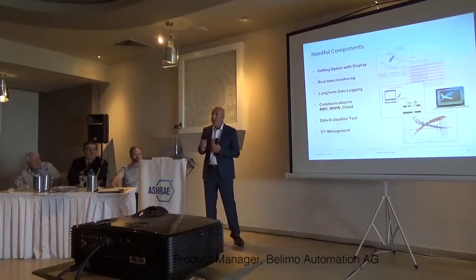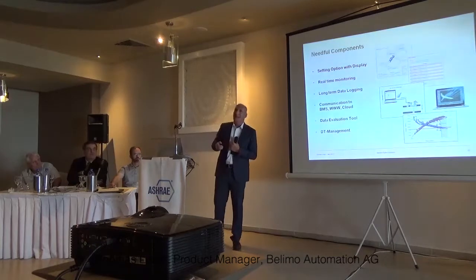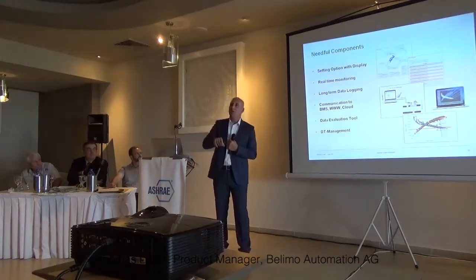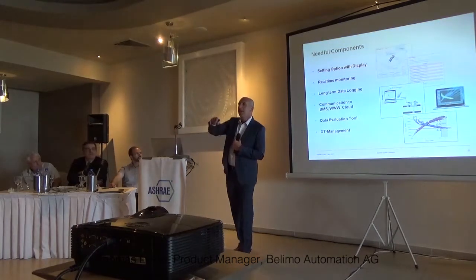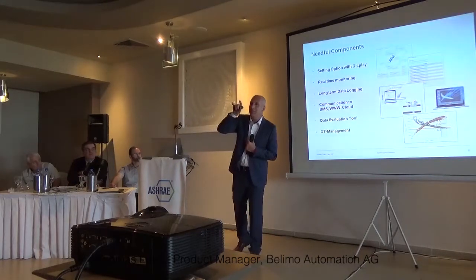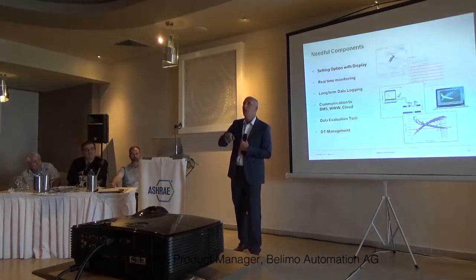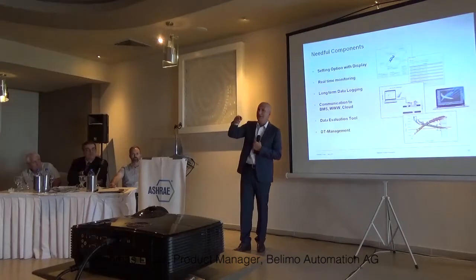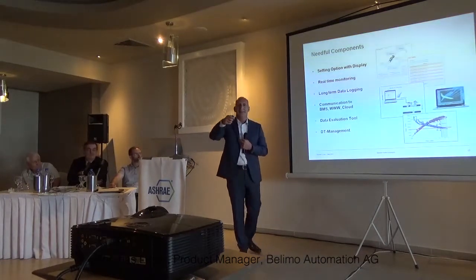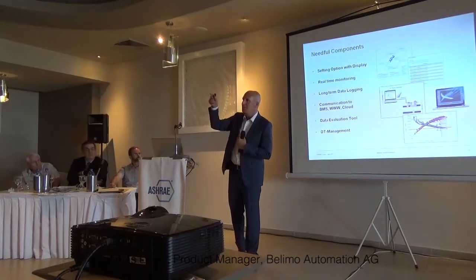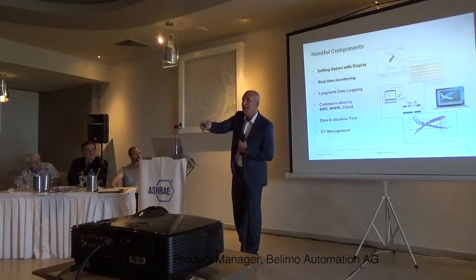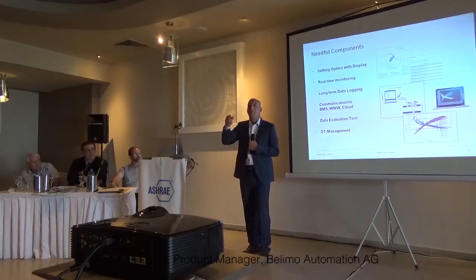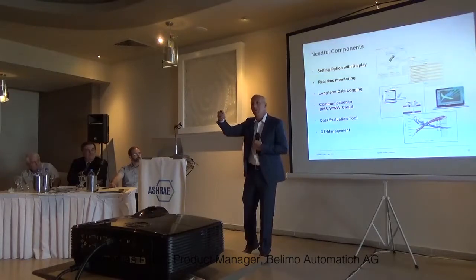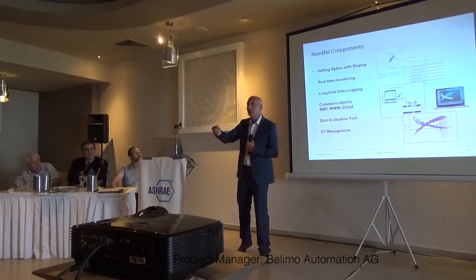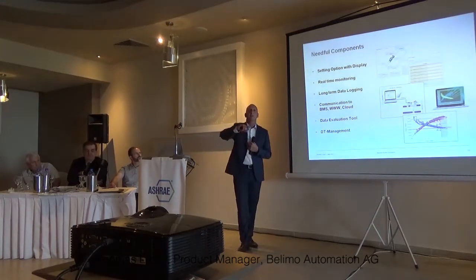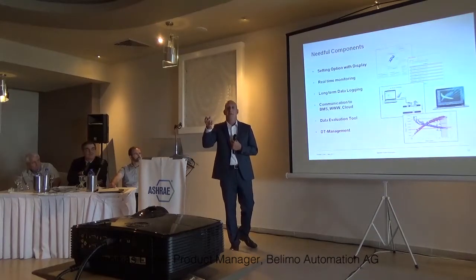What else would be important to have? The possibility to parameterize these valves, to give it a specific flow amount. Let's say I need in winter time on this specific room 100 liters, but in summertime I would need much more. That means 130, 140. And I need the possibility to change this very easily.